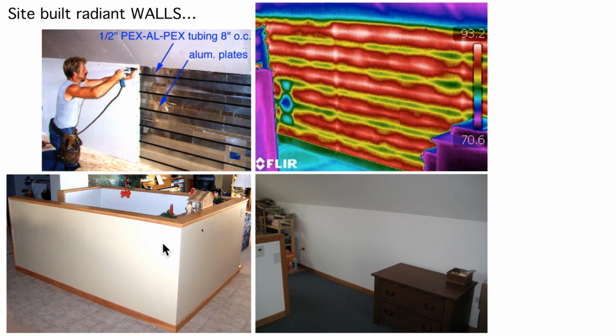And you might be wondering, what's this? Well, it's a wall around a stairwell. And this wall here and this wall here have that same system installed. So you can be very creative with these radiant walls. You don't necessarily have to heat the entire building with radiant walls, but sometimes there are surfaces that are going to remain exposed. In other words, we don't have a sofa, for example, that pushes right up tight against that wall. And that's an ideal surface to create a radiant panel.